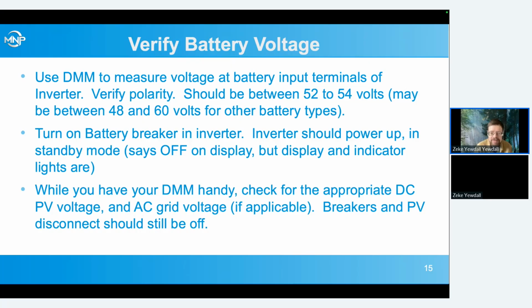While we've got our multimeter handy, this is a good time to check and make sure our DC PV voltage and our AC grid voltage are appropriate. The PV disconnect and the breakers should still be off, but we can check and make sure we've got the right voltage coming in from outside.